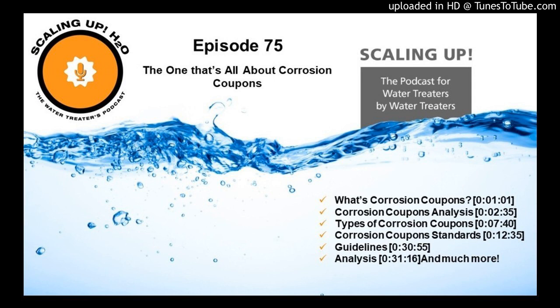that we are collecting. So what we want to do is make sure that the water comes up from the bottom and out through the top. So when you're orienting your corrosion coupon holder, that's how you want to do it. And if you think about that, that makes a lot of sense, because the reason we do that is we want to purge all the air out of it. Then the corrosion coupon is put on a holder.